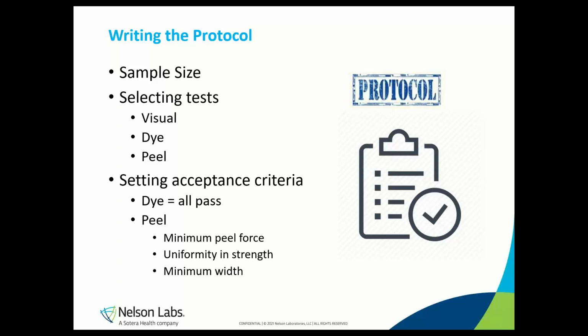And this type of study would show that regardless of where on the sealer the seal was made, you would get the same seal strength. And it's probably more important if the packages will be sealed manually, where placement on the sealer can be more varied. A visual inspection element is often added to document the visual characteristics of the seal are acceptable, but visual inspection alone would not be sufficient to demonstrate seal integrity.